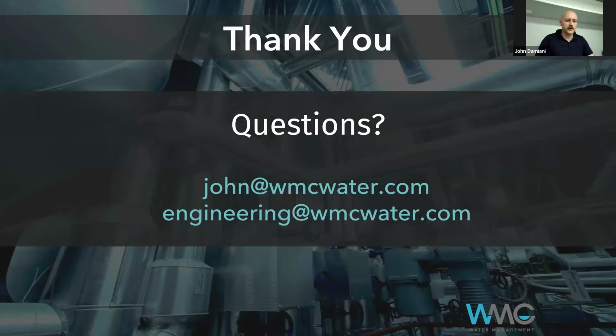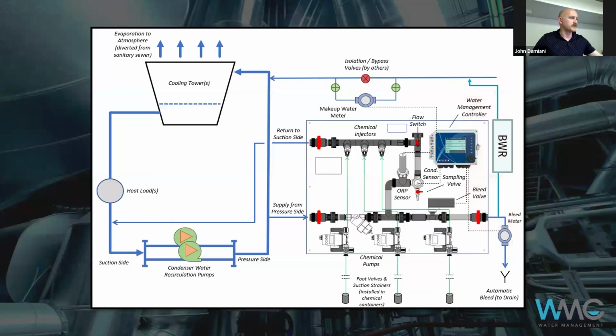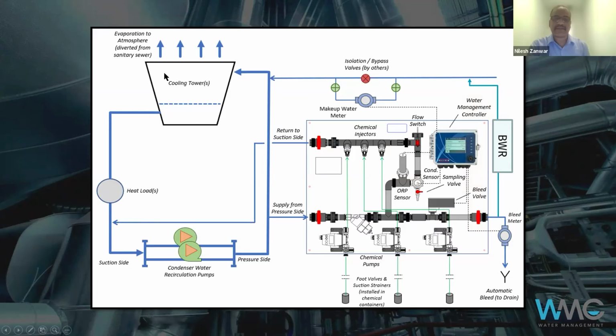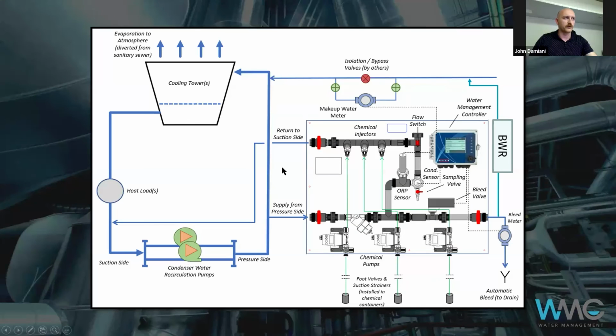Treating wastewater? Yeah, a closed circuit fluid cooler. We call those fluid coolers. So basically, if I go back to a diagram, instead of an open cooling tower where you're directly using the condenser water on your load, I don't know if you can see my mouse cursor, but yes, I can. Okay. So where you're directly using the condenser water to cool your load, you've got what's called a fluid cooler.